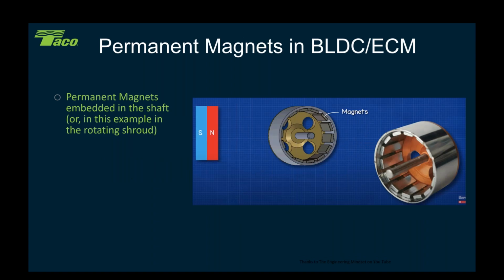Now, in this particular example, it's not the shaft. This is a rotating housing. So the shaft is stationary, and the rotating part is the shroud. Just a different type of motor technology. These are real common in ceiling fans. In ceiling fans, the shaft is locked and the housing actually rotates, because the shaft is what your light set and all that stuff is mounted to, and that's what's attached to the ceiling. It's the shroud around it that rotates. So that's the way a ceiling fan is set up.